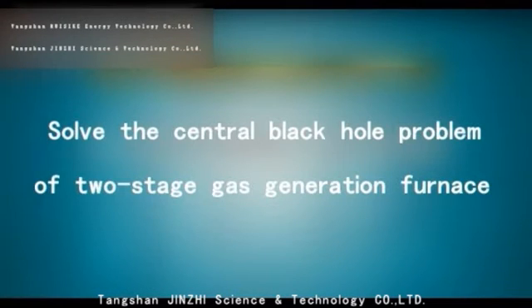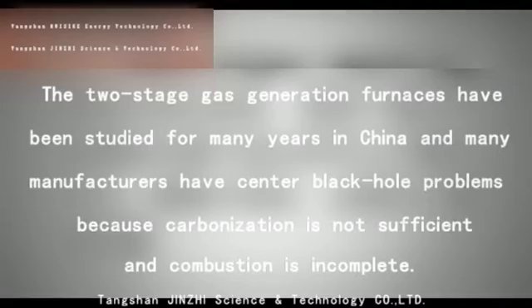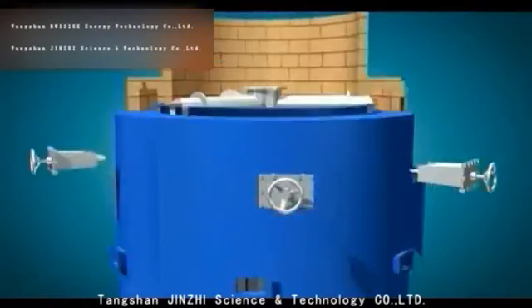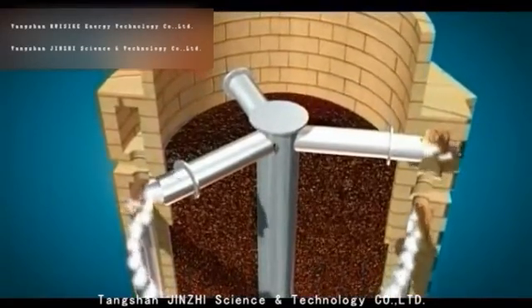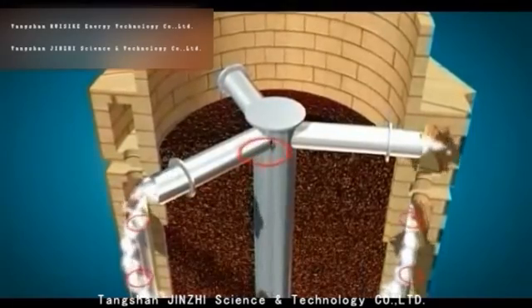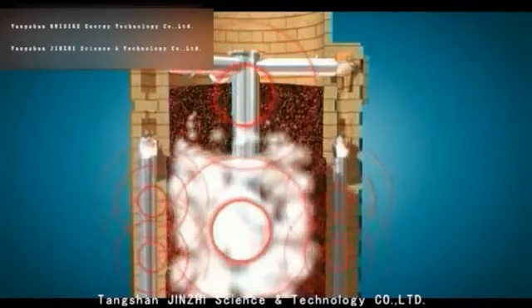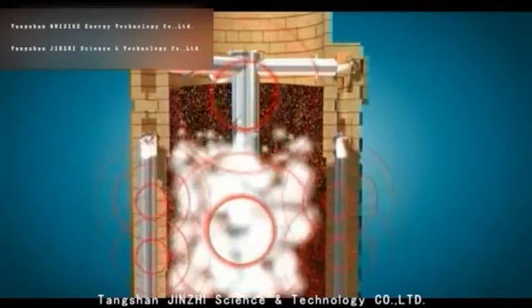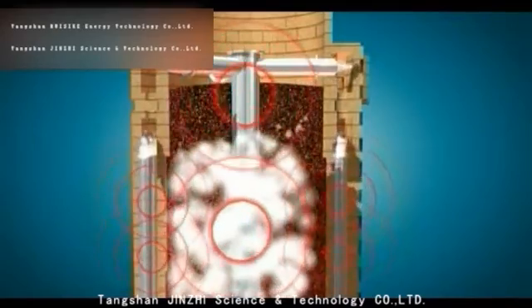Combustion center black hole problem: the two-stage gas generation furnaces have been studied for many years in China. Many manufacturers have the center black hole problem because carbonization is not sufficient and combustion is incomplete. After many years of experiments and research, our company has arranged a stainless steel center pipe and 36 surrounding gas flow channels in the carbonization section of the two-stage gas generation furnace to form inner and outer ring radiation heat sources. This heat source and the rising gas generated by the lower stage heat the coal to improve the gas quality, allowing carbon to be uniformly coked to avoid the gasification center black hole problem existing in two-stage gas generation furnaces made in China.